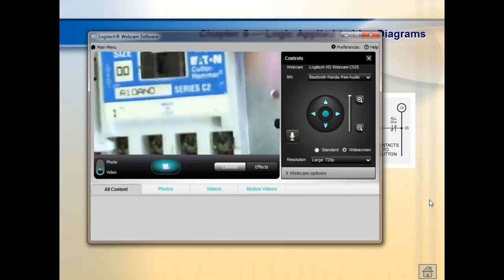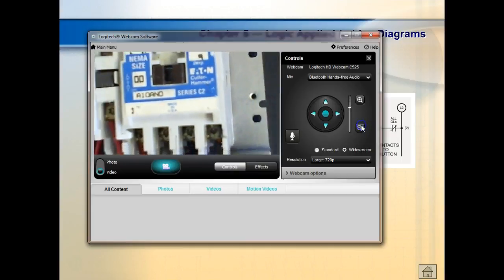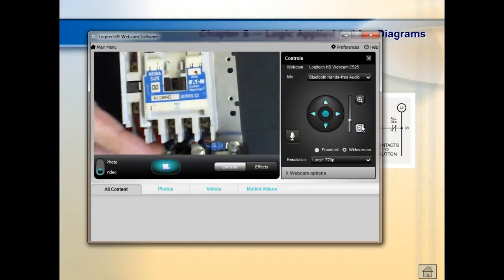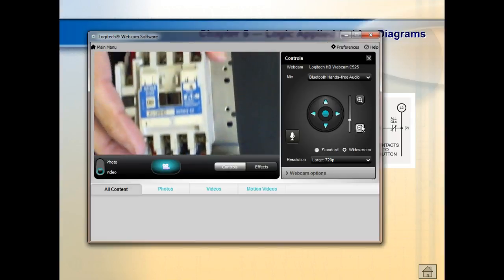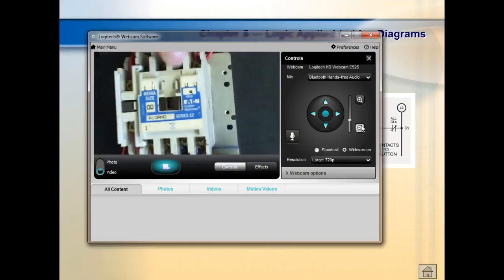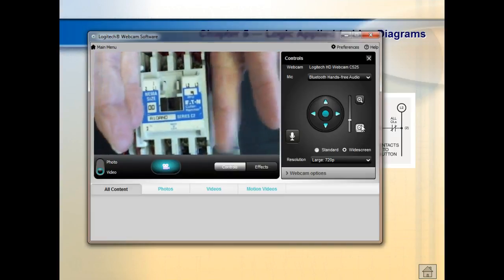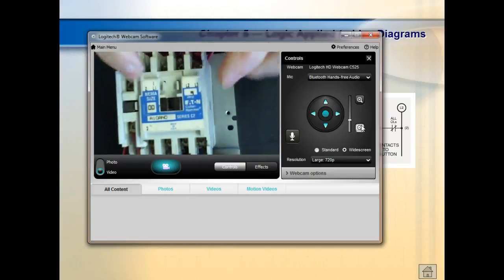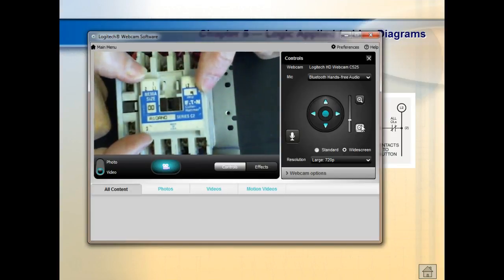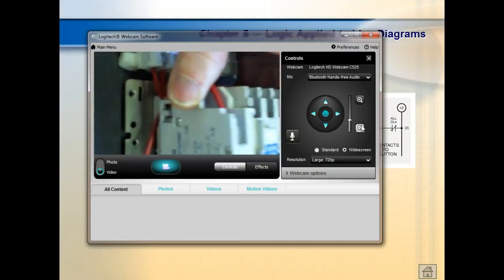So notice, let me zoom out. Well, they don't have to normally be on the side. Normally, we call our 3-phase L1, L2, L3. So here's your power contacts, L1, L2, L3. Then I've got this contact right here labeled 2, 3. That's an auxiliary contact that's built into the relay. So these are your power contacts right here. These are auxiliary contacts. Now this comes in this relay block when you buy it. So if you buy this part number for this relay, you get 3 power contacts and 1 auxiliary contact. And then you have the ability to add another auxiliary contact, which is over here on the side.